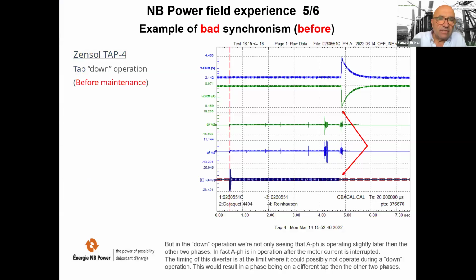So here they have discovered another thing, but in the down operation. Before maintenance, we are not only seeing that A phase is operating slightly later than the other two phases. In fact, A phase is in operation after the motor current is interrupted. Here I have shown this with the red arrow, that you have the impact, which occurred after the end of the current. And the timing of this diverter is at the limit where it could possibly not operate during a down operation. And this would result in a phase being on a different tap than the other two phases.